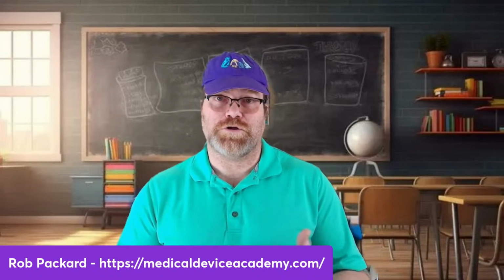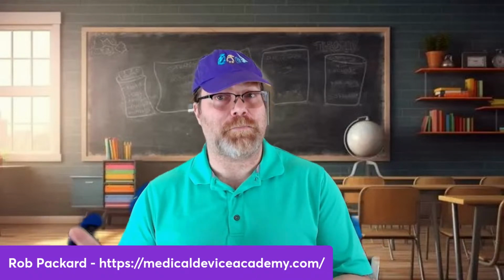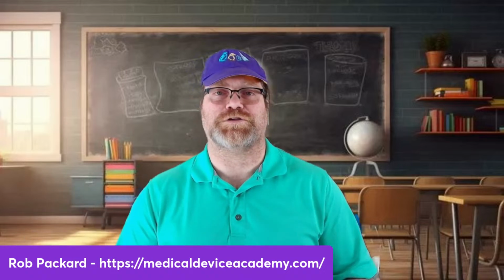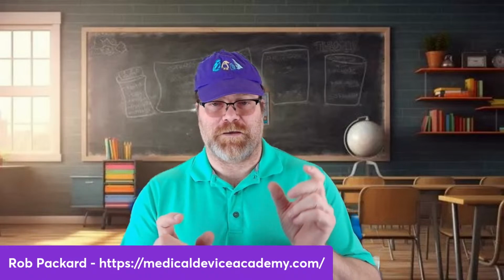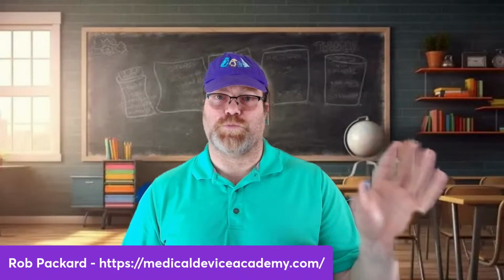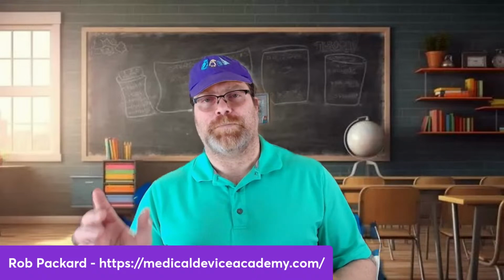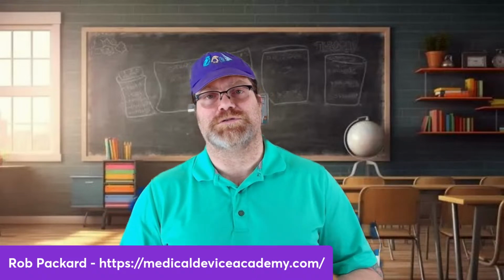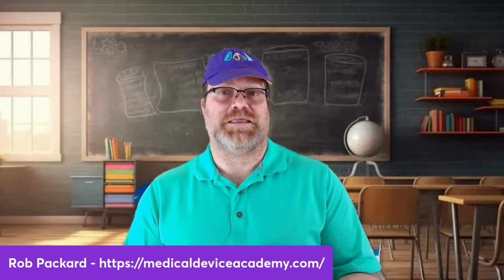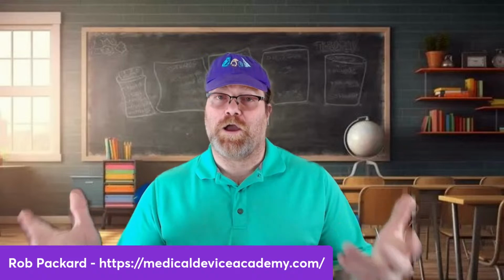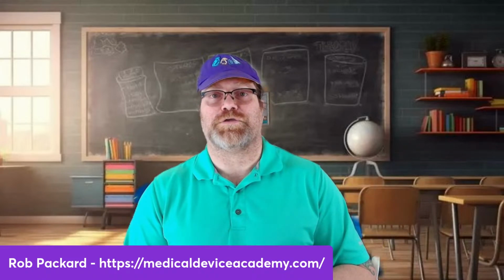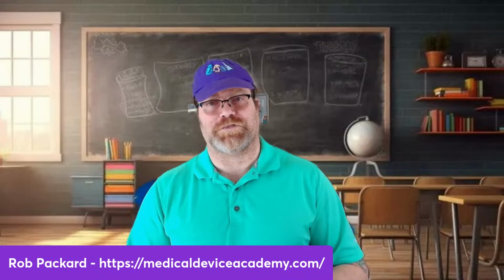So you want to learn how to implement probably a serialized approach for those types of software, and have a DI that tells you what version, what manufacturer, what model of software, but the PI portion is going to be the individual delivery to that customer or that individual workstation. So I hope that helps you. For those of you that were interested in how you do it for software as a medical device, I hope that helps.